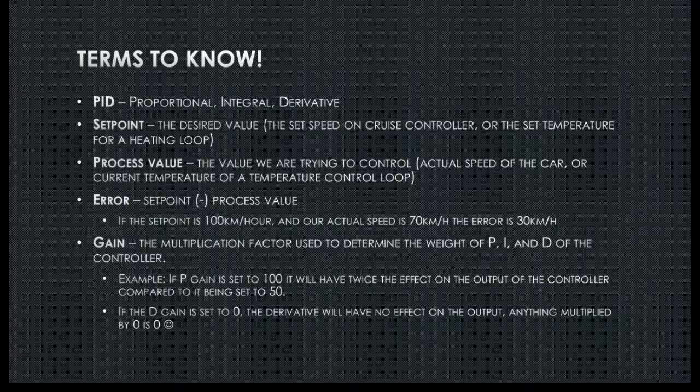Gain. You just heard me say the proportional gain, integral gain, and derivative gain. The gain is just a multiplication factor used in the calculation of the PID controller. For example, if the P gain is set to 100, the proportional will have twice the effect on the output of the controller as if the P gain was set to 50. These numbers don't necessarily represent anything — they're a unitless number, and just a gain or multiplication factor that when increased will have a higher effect on the controller, and when decreased will have less of an effect.